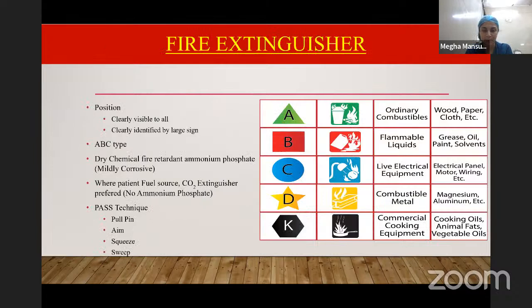A fire extinguisher should always be present in an operating room. Its position should be clearly visible to all, and it should be clearly identified by a large sign. Fire extinguishers in ORs should be of the ABC type, which means that they should work against ordinary combustibles, flammable liquids, as well as live electrical equipment. The dry chemical fire retardant used most commonly in fire extinguishers is ammonium phosphate, which is mildly corrosive. Hence, where the patient is the fuel source, a CO2 fire extinguisher is preferred as it does not contain ammonium phosphate. The correct technique to use a fire extinguisher is the PASS technique. The acronym stands for pull, aim, squeeze, and sweep.